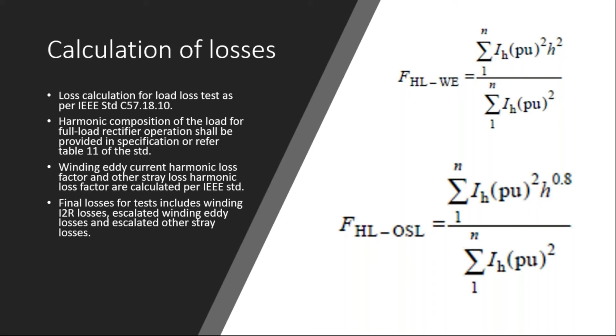With those harmonics, we need to do the calculations for the winding eddy harmonic enhancement factor and then the stray loss harmonic enhancement factor. These two are very important for these small transformers and special application design, and this takes into account the percentage of each harmonic current. If the harmonic current requirement is not provided in the specification, then this becomes tricky, and we have to use table 11. As per the standard, table 11 is kind of a conservative number. So if you don't specify the correct amount of harmonics, either your transformer design can be very expensive, or if your system has more, then the transformer will be inadequate in terms of rating to dissipate the losses. So these are all calculated on top of the I2R requirement.